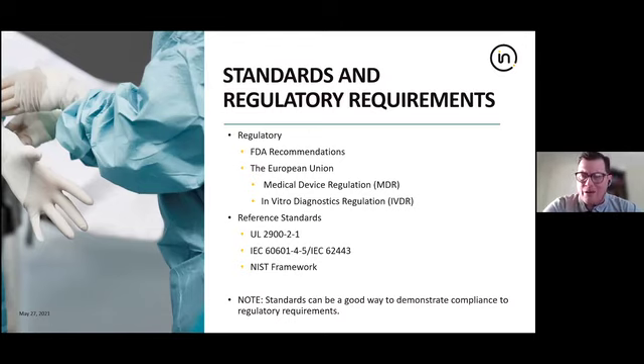60601-4-5 really leverages the IEC 62443-4-1 and introduces security level controls into the standard. So it's a very unique standard that it's going to be a game changer for a lot of manufacturers. 62443 is a very good standard. They're both good standards, not advocating one or the other, but they're both very well written standards. And the fact of looking at security levels, it really depends on the risk factor or the risk management that a device manufacturer has on their product.